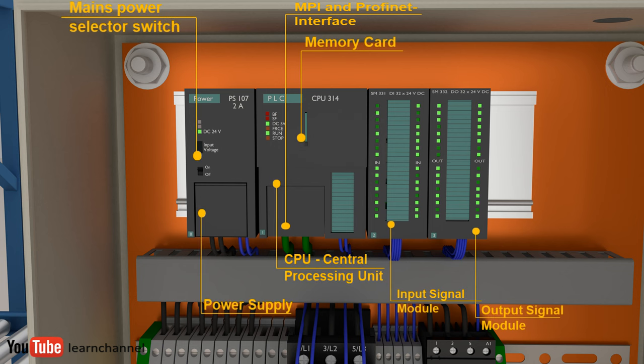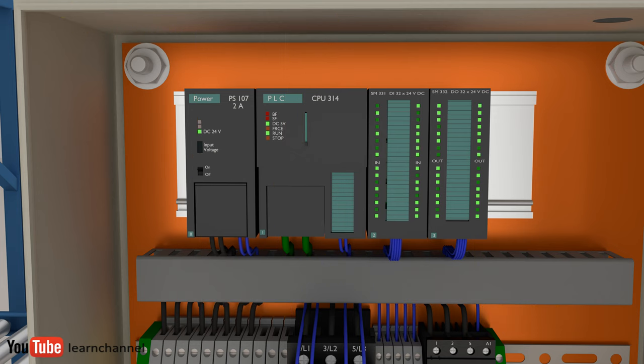The power supply module is placed on the left, followed by the central processing unit, or CPU, and the input and output cards. Depending on the application, further modules such as communication panels or motor control are arranged on the right. The mounting locations, i.e. slots, are numbered from left to right in increasing order.